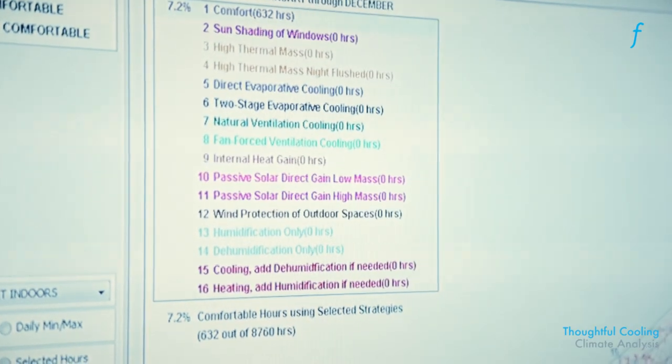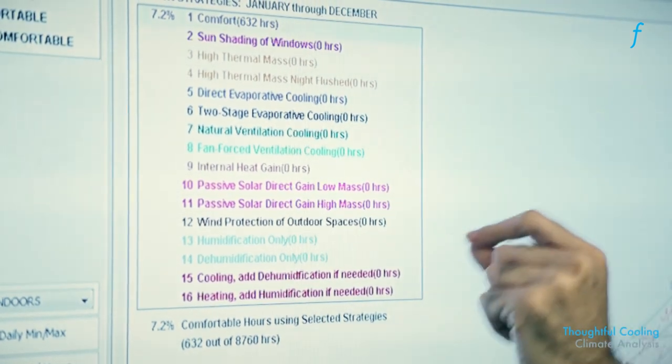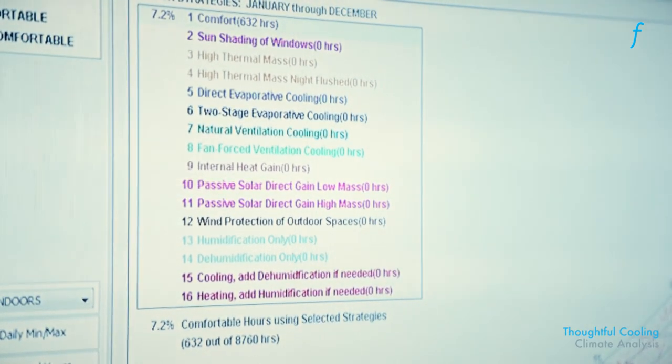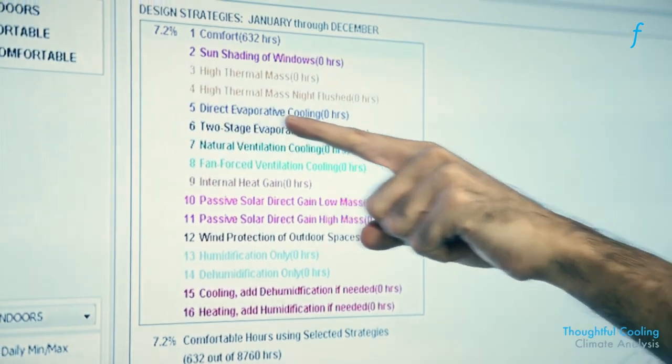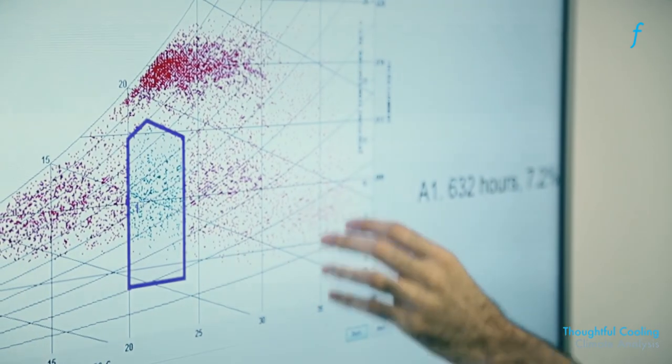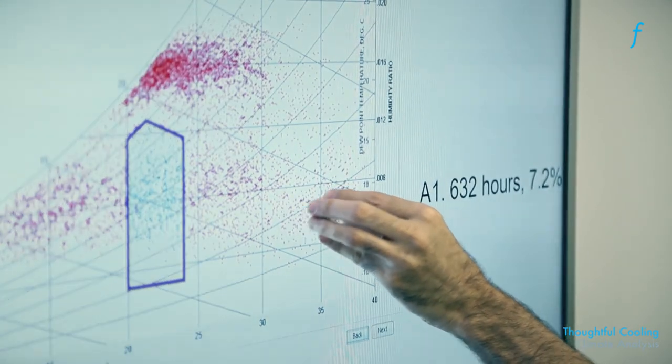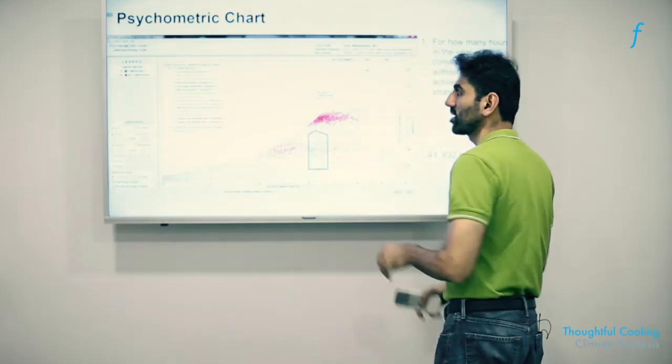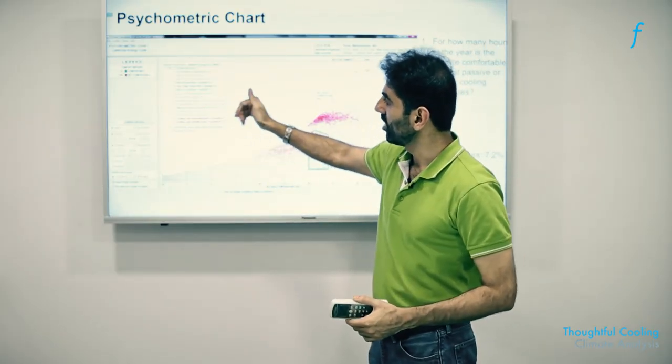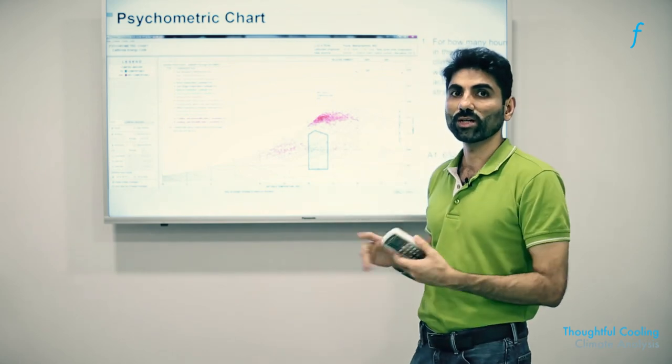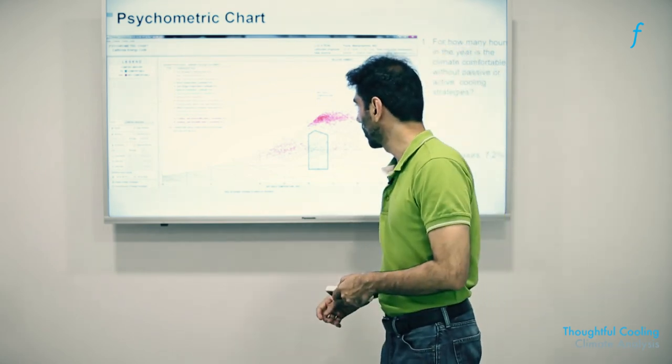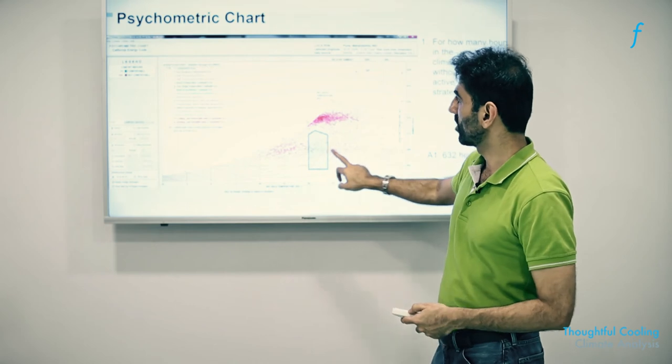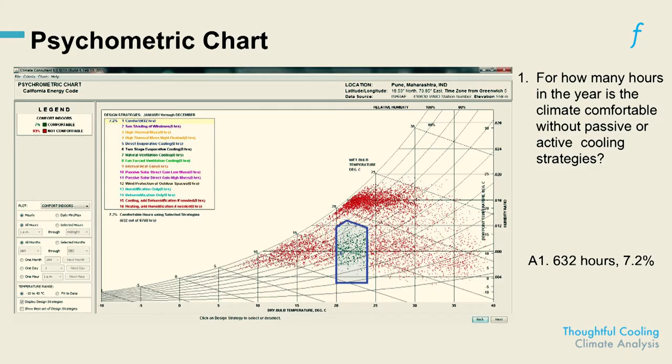And when you turn this feature on, it tells you how many hours will each of these strategies be useful for. So for example, it tells us direct evaporative cooling will most likely work here. What is the number of hours where I can use that process to take these dots and bring them into the center? This will give me a sense of how effective a certain strategy will be, which ones I should discard, which ones I should focus on, so on and so forth. And it also tells you the comfortable hours. So the comfortable hours in this case are 7.2 percent of the hours are already within the comfort zone in the city.